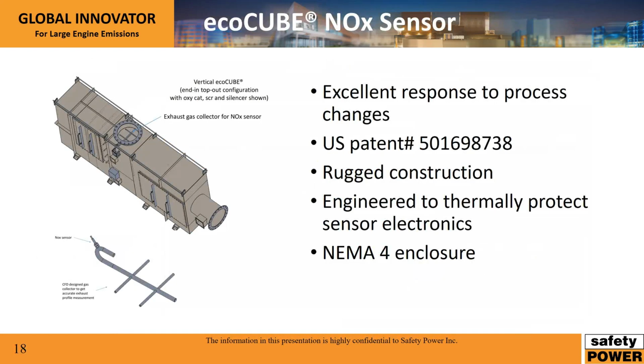This is a patented design as well. One unique thing you'll notice is the shape of the sensor itself. The reason for this is we have 7 separate holes in different locations, which allows for an average measurement of the whole exhaust stream, as opposed to a point measurement, making it a much more accurate measurement overall.